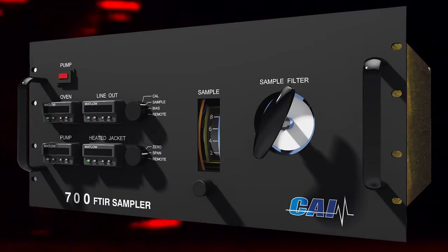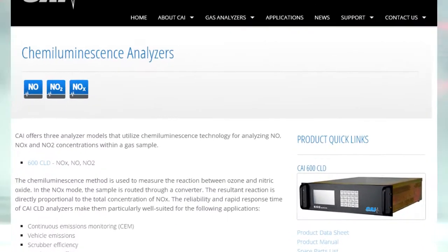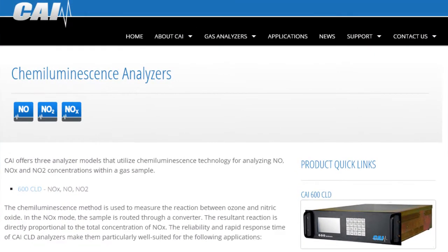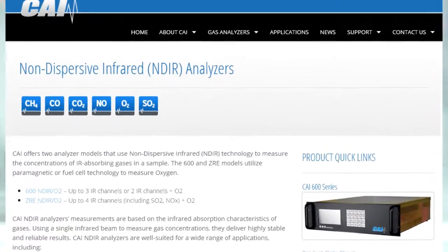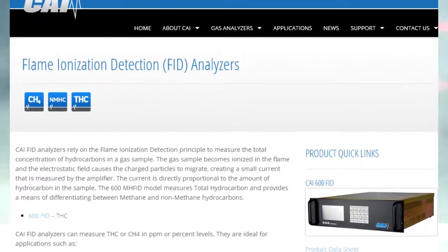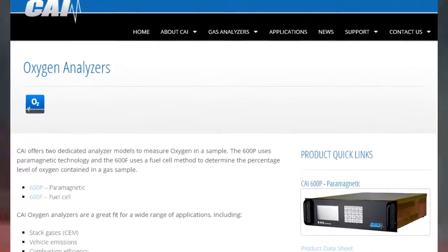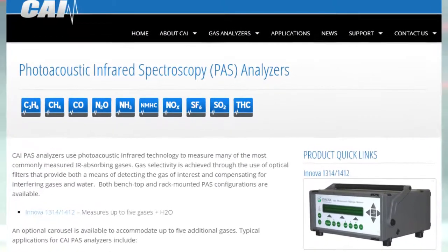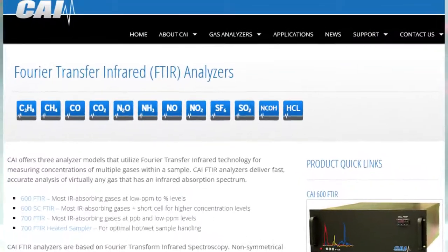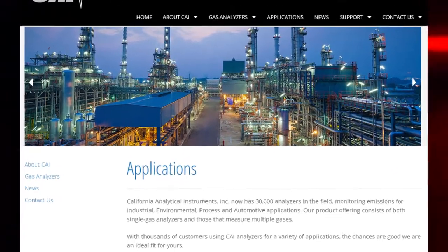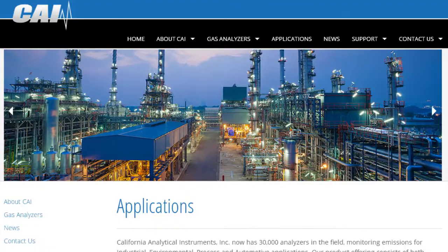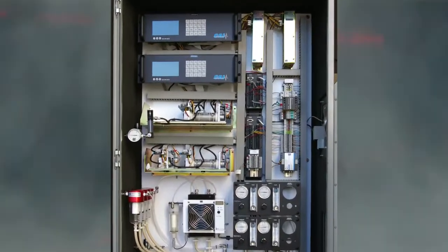CAI analyzers utilize proven technologies such as chemiluminescence, non-dispersive infrared, flame ionization detection, paramagnetic, photoacoustic infrared spectroscopy and Fourier transform infrared for consistent accurate measurement of virtually any gas.